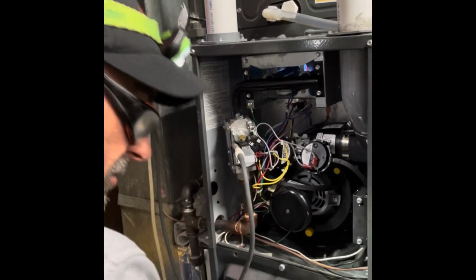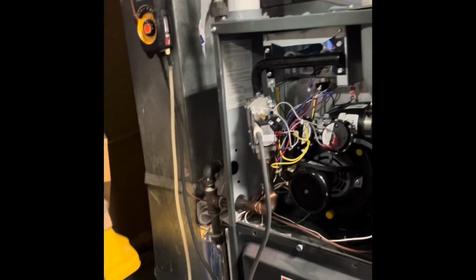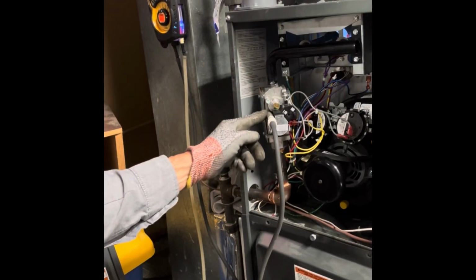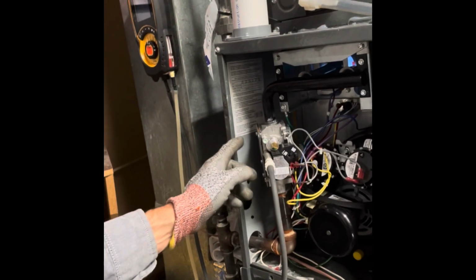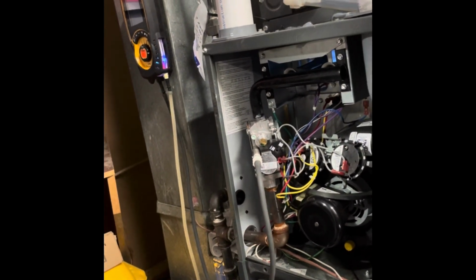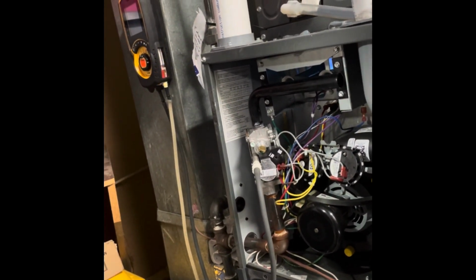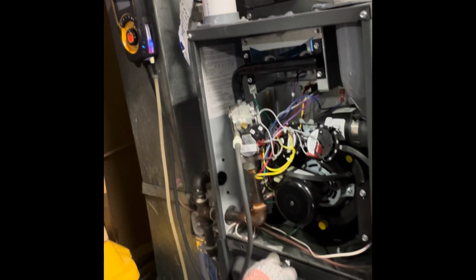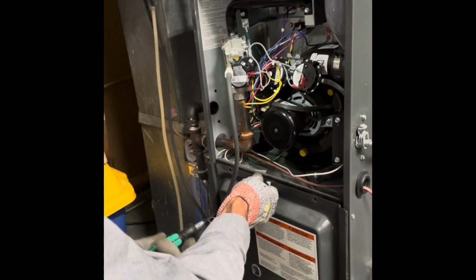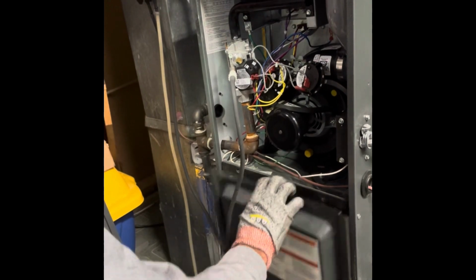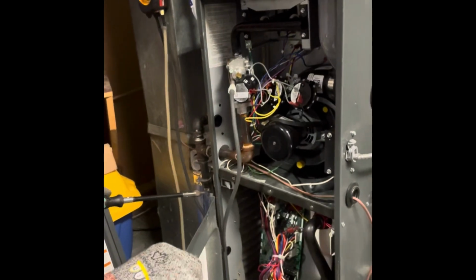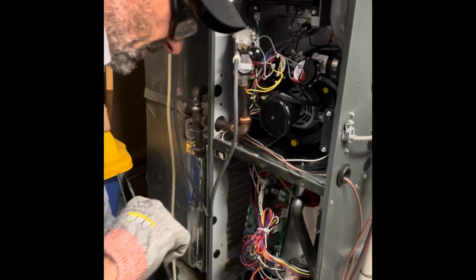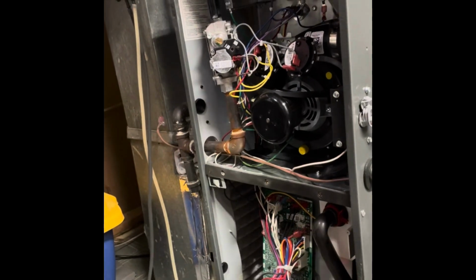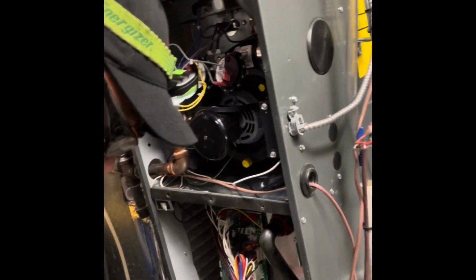So now I'm finished with the maintenance. I've got to put everything back together, and I've got to do a leak test at this valve because I did tap into it. I don't want to be leaking fuel. So I'll take this door off. And the furnace switch killed the power to the furnace, as it should. What I want to do now is get my Allen keys, and I just want to check both ports for this valve.